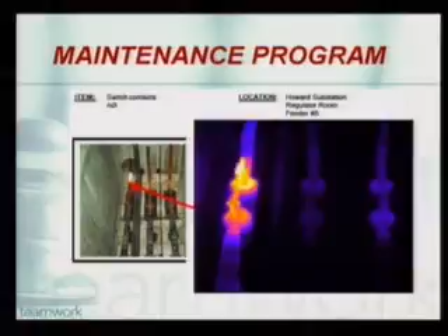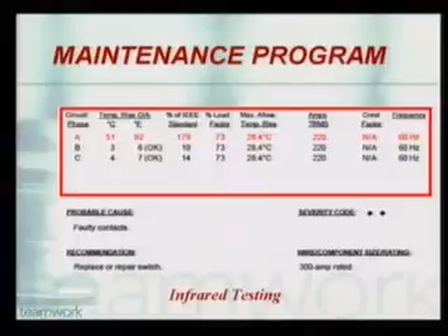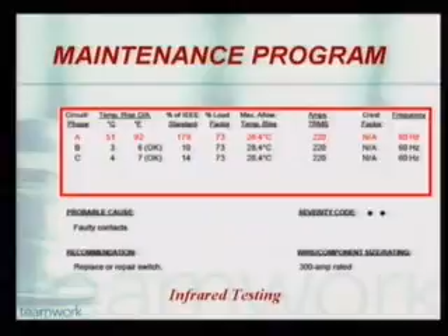These are the causes of that. It's a loose connection that may have been due to vibration, or when we load the system, the heating and cooling causes the loose connection to occur. And we use that not only for buses. I'm sorry, in this particular example, like I said, phase A was pretty hot, and this is the data that we get from the actual report. It gives us the temperature difference between the phase that's failing versus the other two phases, which are normal. And the recommendation we follow is replace or repair. And what we do is we take this out of service until such point that we can get to it.